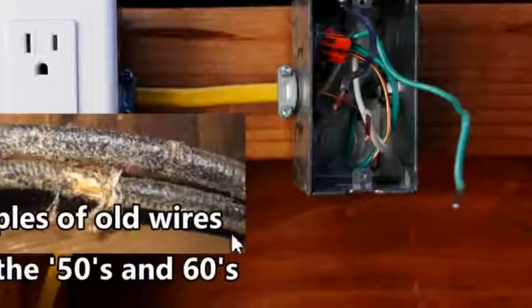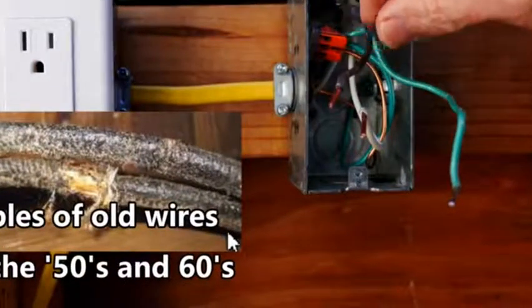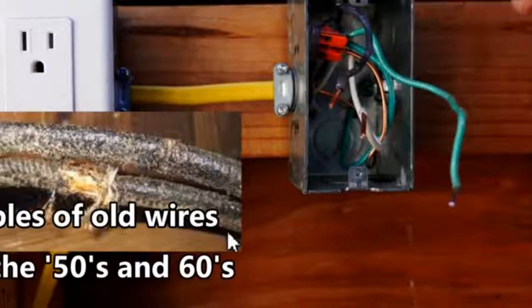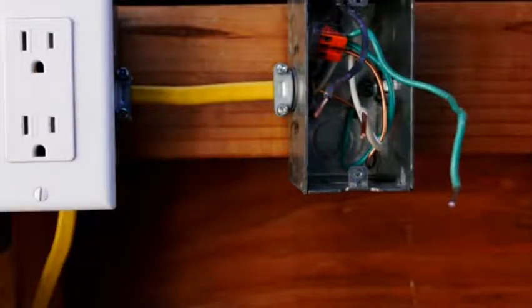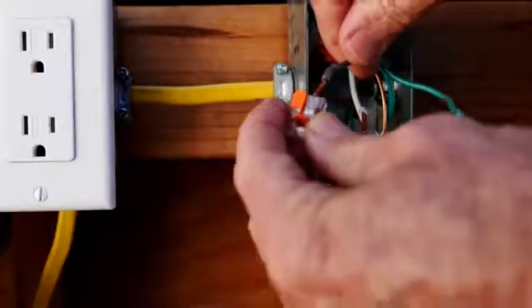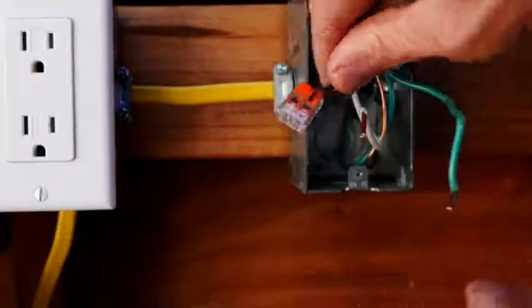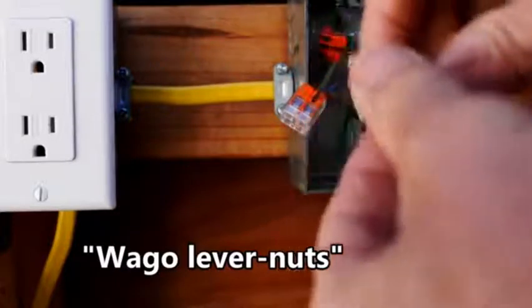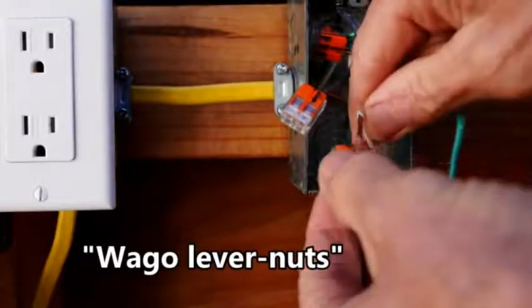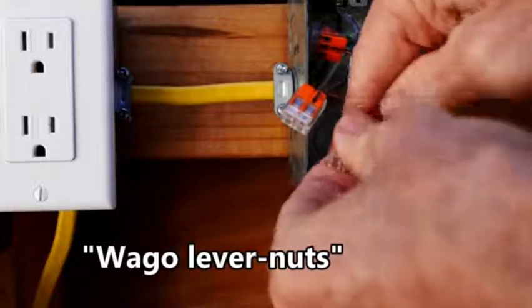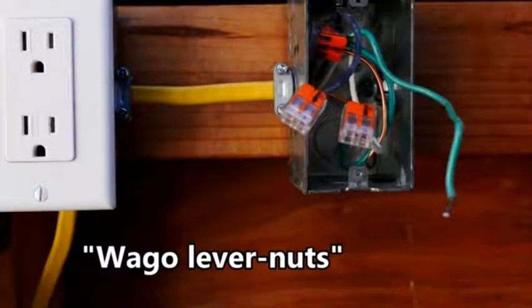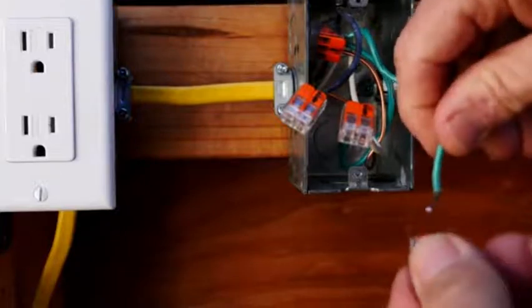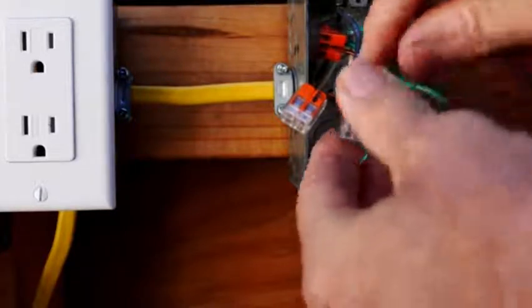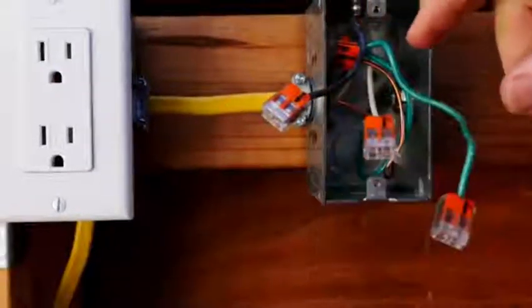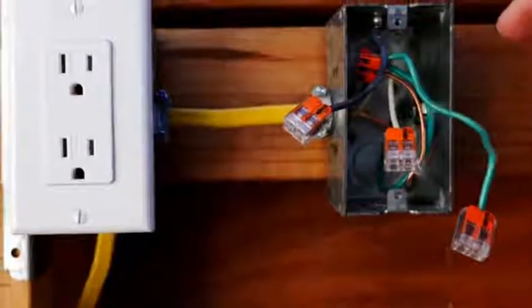And sometimes people just go ahead and guess, and they guess wrong, and you get a reverse polarity receptacle. So I'm going to show you how to identify which is the hot and which is the neutral. And of course the electricity's off. These are called Wago lever nuts. I'm going to put them on the ends of the wires for safety, and I'm going to temporarily turn on the electricity and make a test to determine which is the hot and which is the neutral.